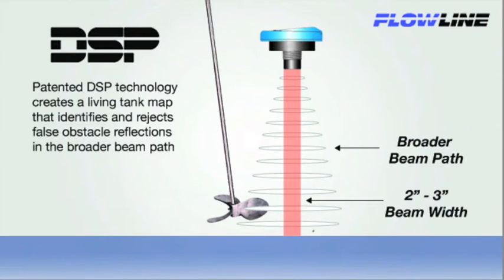DSP is able to filter out false obstacle reflections and track the true level of liquid. This gives Flowline ultrasonic sensors a 2-3 inch minimum beam width across the measurement range and increases the installation flexibility of the sensor. This allows Flowline ultrasonic sensors to measure reliably in tight places or applications with obstructions.